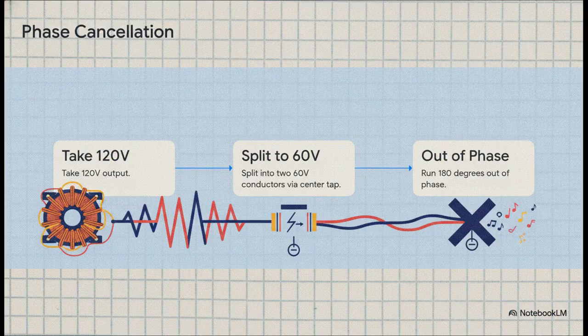To fix this, engineers use a beautifully elegant piece of equipment, the balanced toroidal isolation transformer. The math behind it is brilliant but simple. First, it takes the standard 120-volt output. Second, it uses a center-tapped winding connected to ground to split that into two 60-volt conductors. And third, it runs those two 60-volt streams exactly 180 degrees out of phase with each other. Because they are perfectly opposite, any common mode noise present on the line is symmetrically canceled out right at the ground junction. It mathematically deletes the hum. It's like magic, but it's just great engineering.